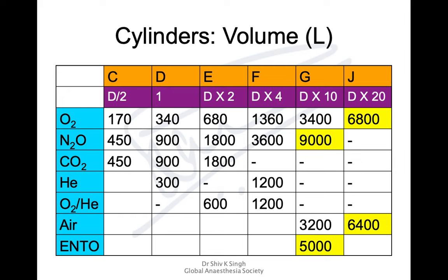For cylinder volumes, there are various sizes. Use D-type as a reference value of 1: E is twice D, F is four times D, G is ten times D, J is twenty times D, and C is half of D. For example, an oxygen D cylinder holds 340 liters: E = 680L, F = 1,360L, G = 3,400L, J = 6,800L. Nitrous oxide and Entonox are available in G type (9,000L and 5,000L respectively), and air in J type (6,400L).